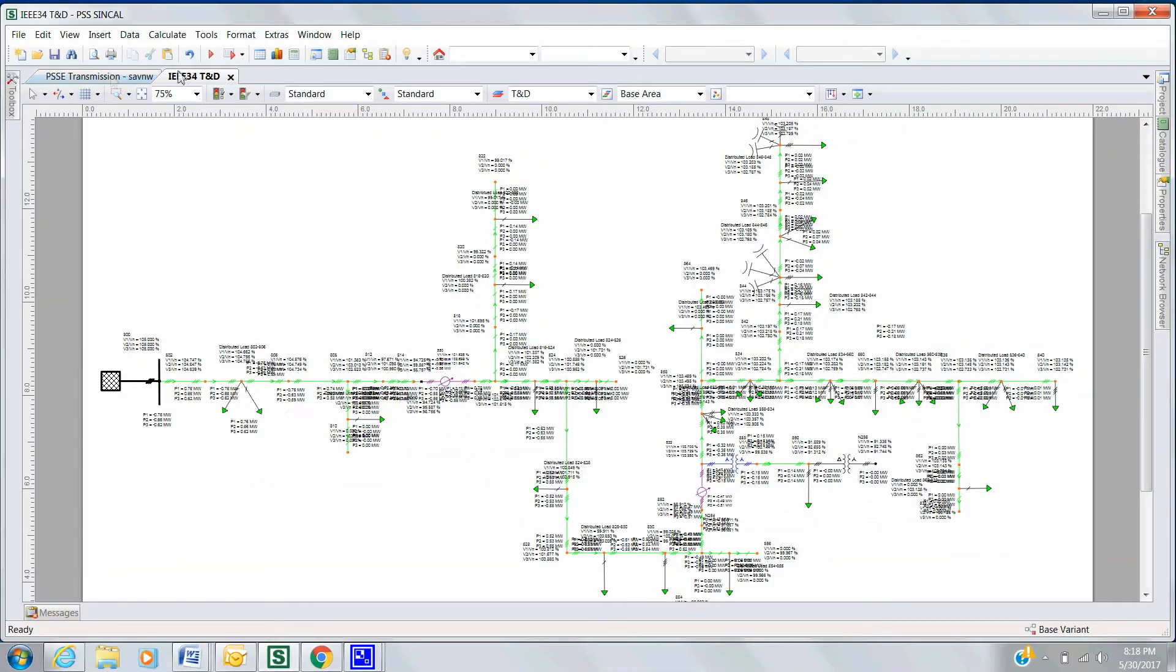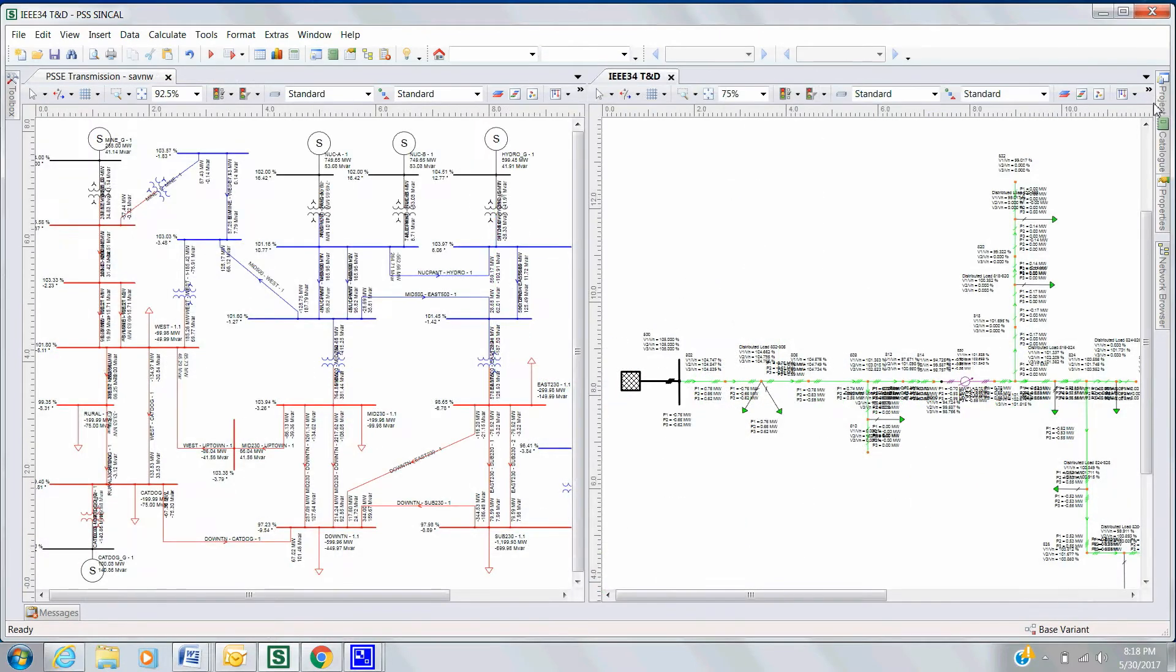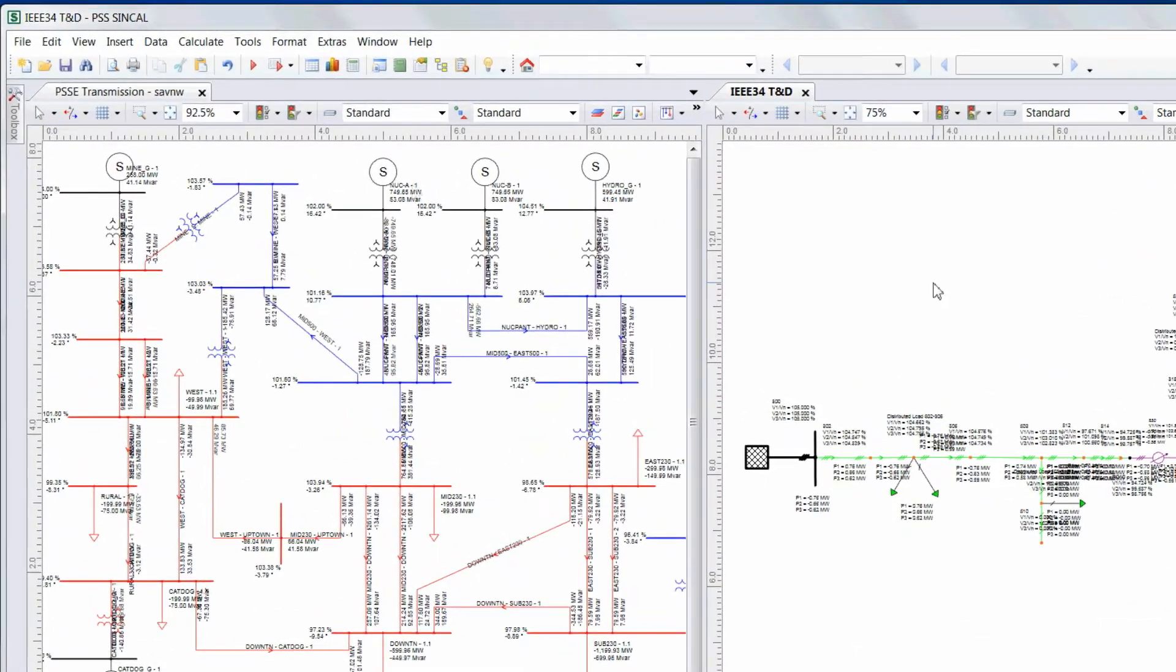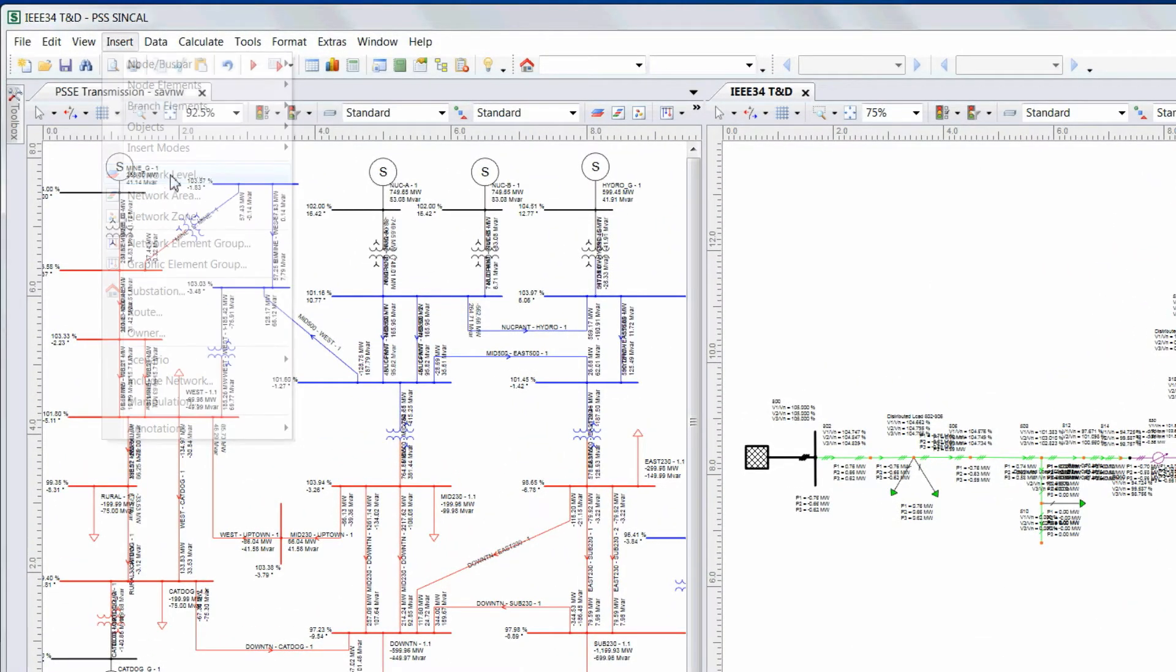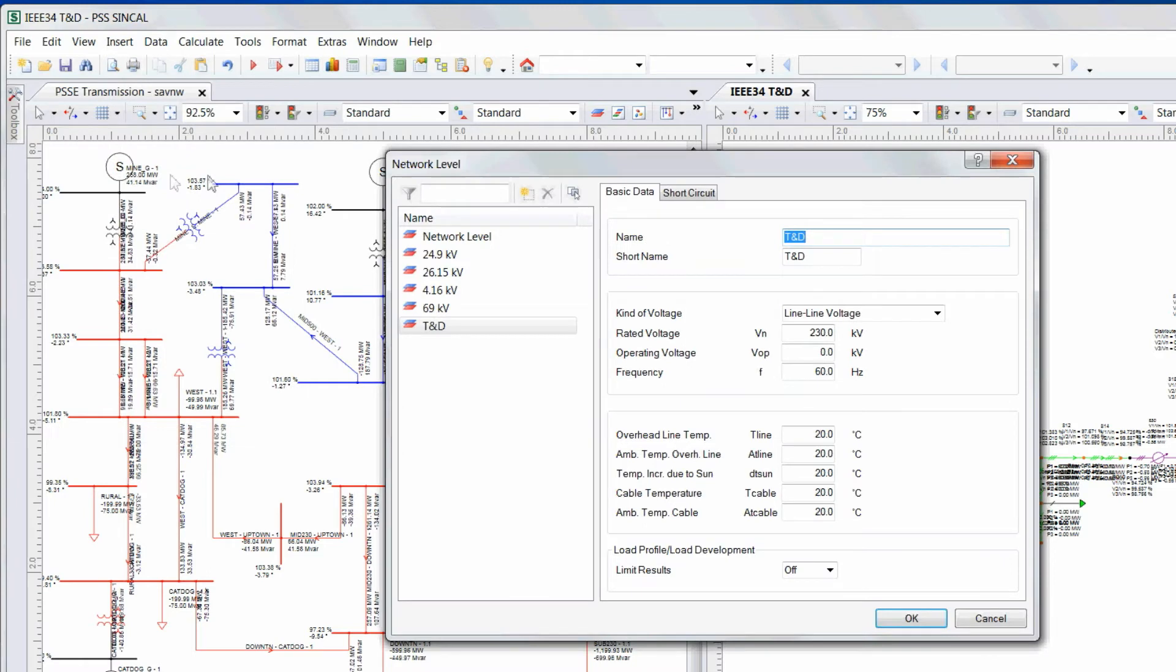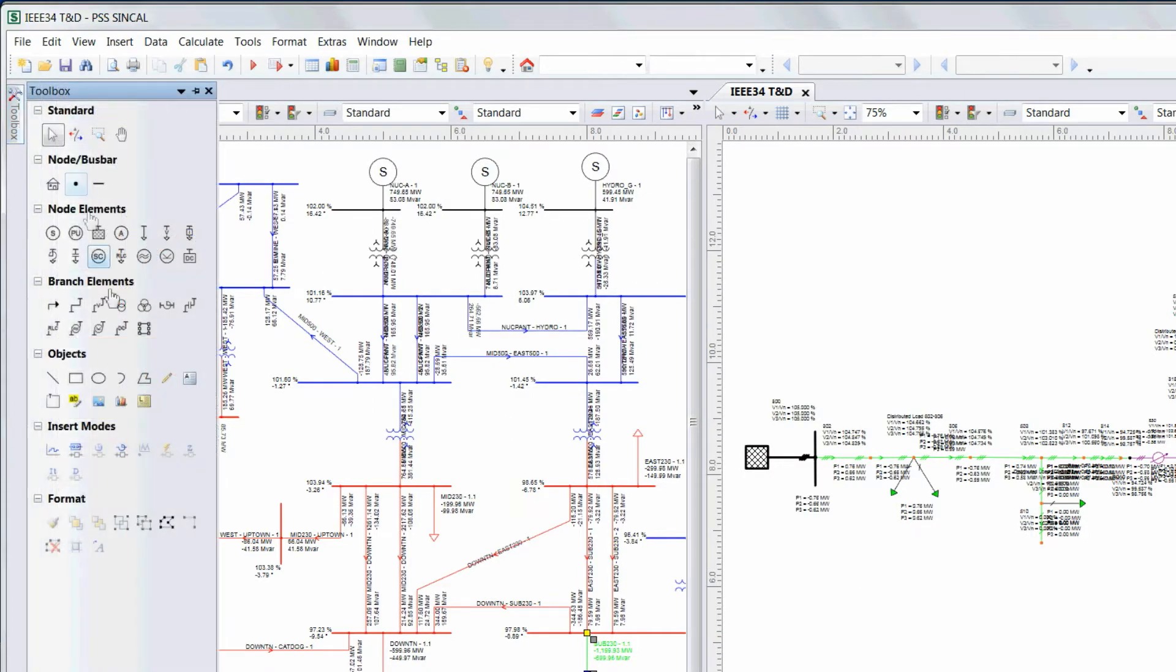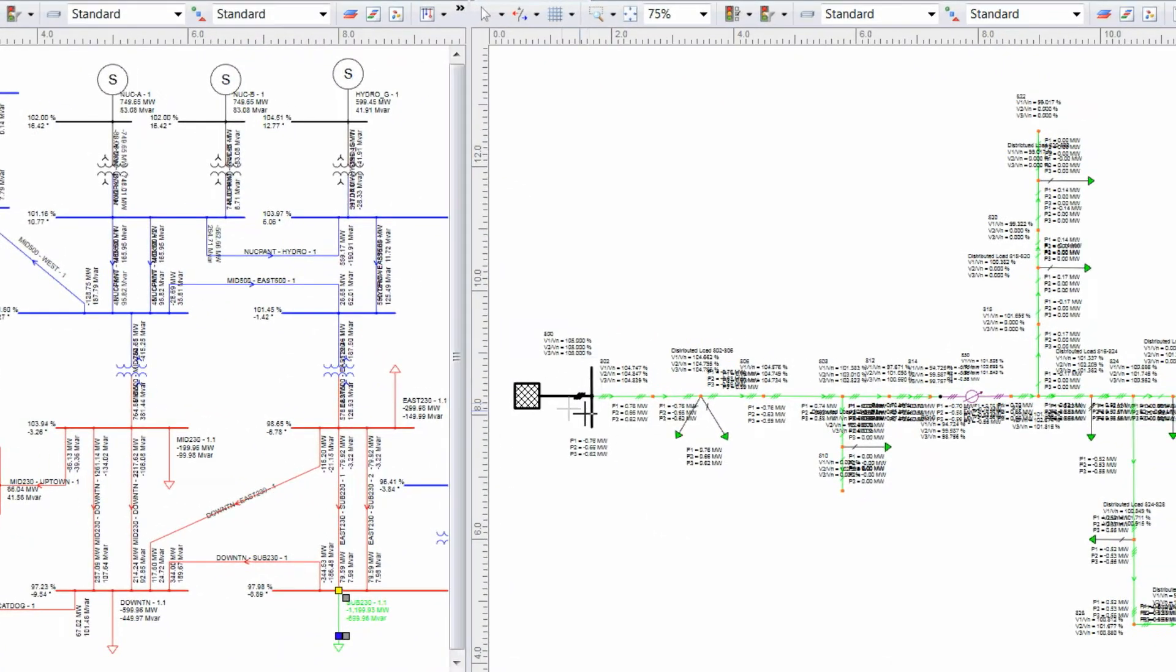Now we can integrate the two models to simulate integrated planning analysis and study the impacts of the low, medium, high voltage simultaneously. In order to integrate the two systems, first create a new voltage level on the distribution network representing 230 kV, and then create a transformer to link the distribution network to the 230 kV transmission network. This can also be done at the transmission side.